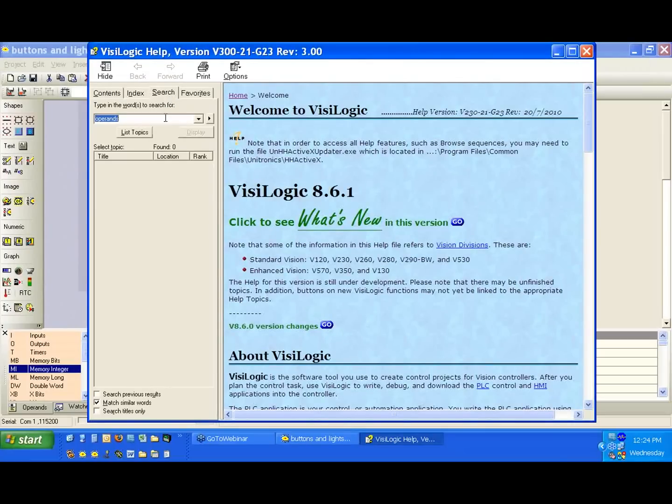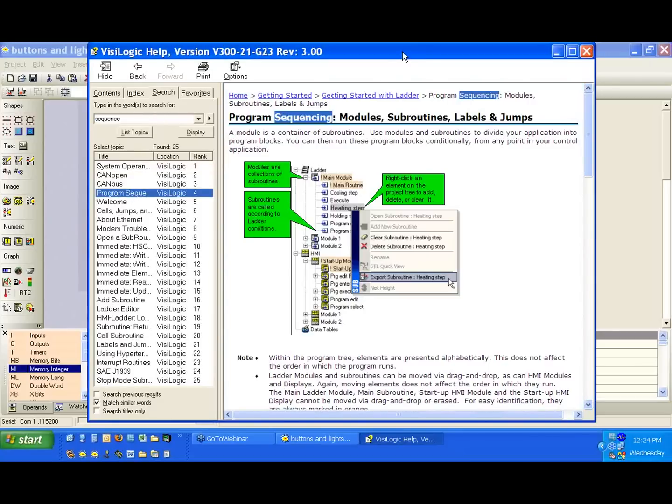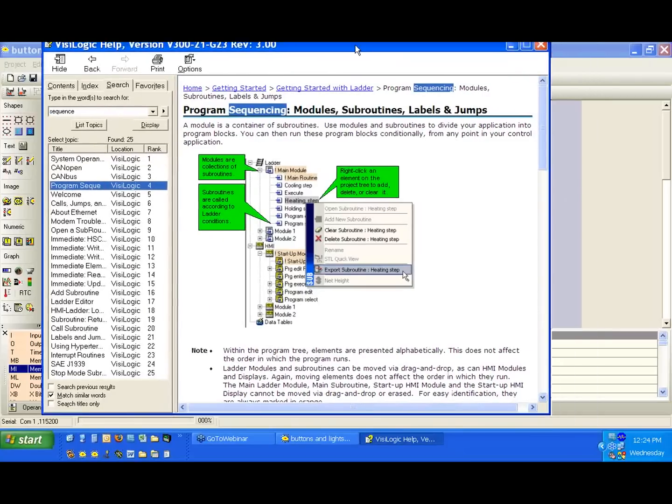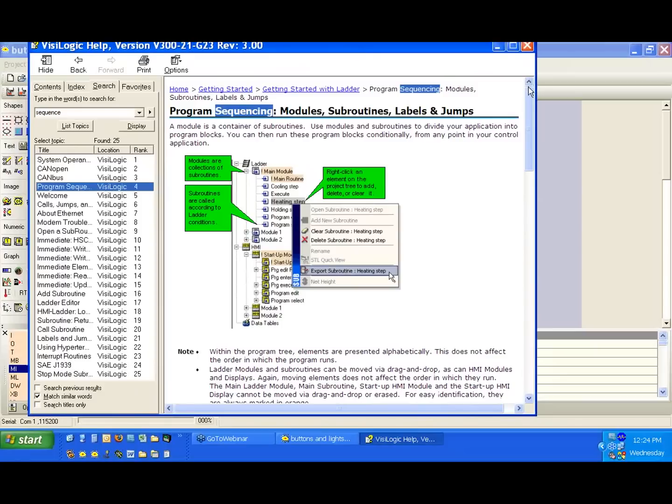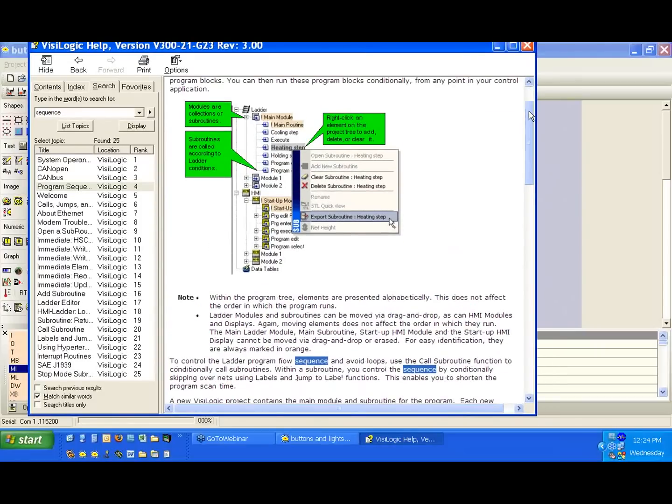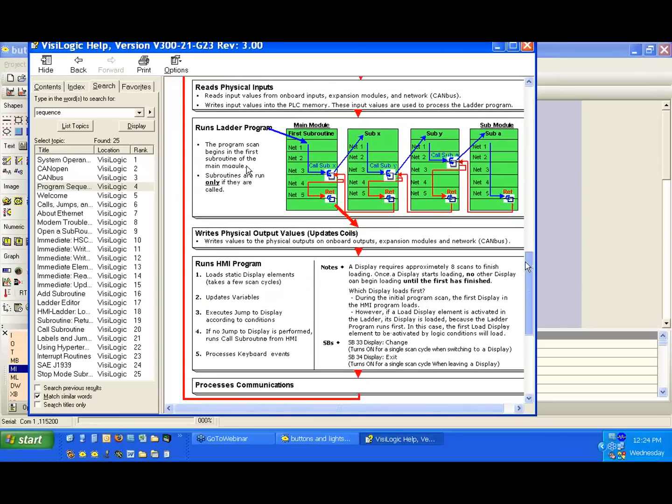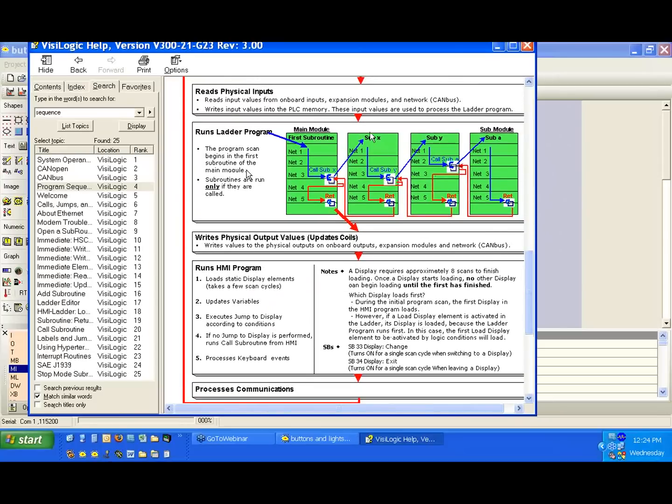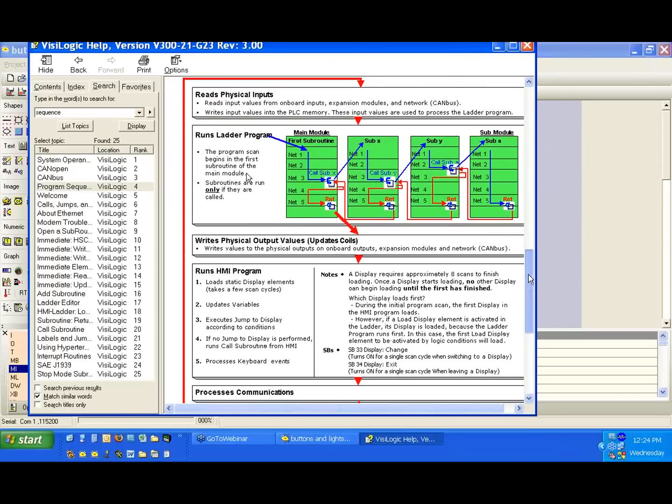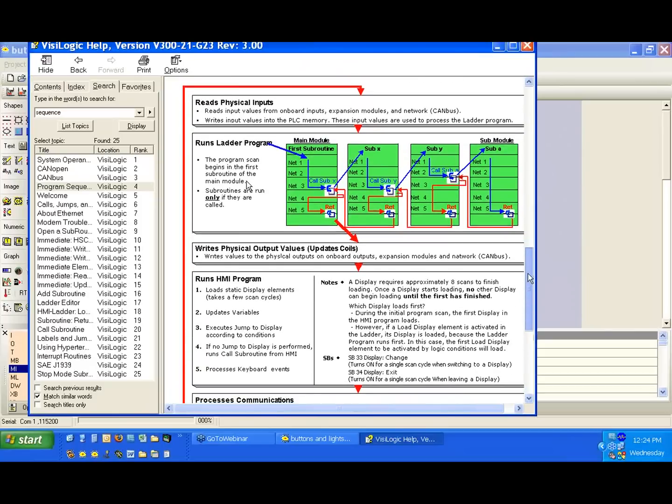Specifically, if we go to search and search for sequence, what we want to bring up is the program sequence. This is something I would advise everyone who is working with the PLC to read and try and understand, it explains the program scan and how it works. So we read the physical inputs, we create a memory table, then we run into the ladder, we'll execute our ladder, and then we update our HMI and our outputs.